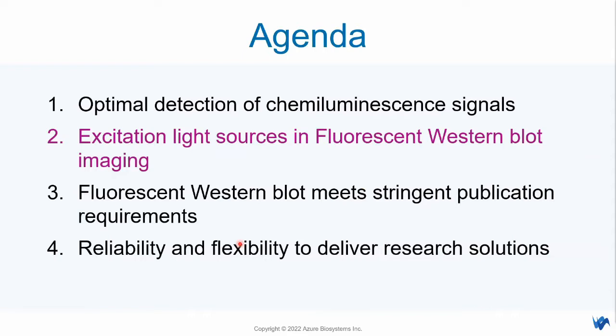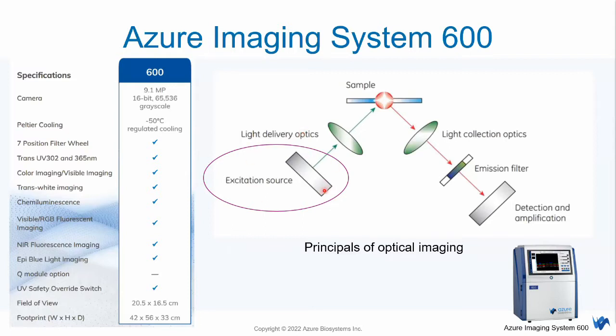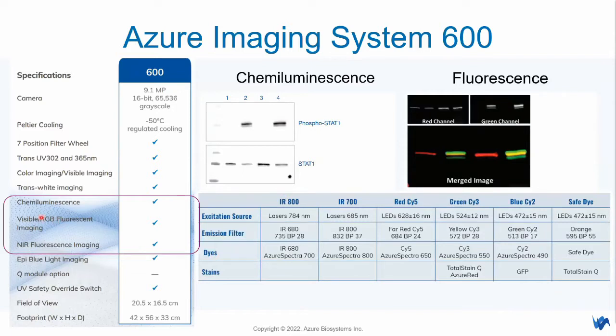Next, we move to excitation light sources. For chemiluminescent western blot, no excitation light sources are needed, but for fluorescence you definitely need them to excite the fluorophore. This system allows you to do RGB and near-infrared fluorescence imaging. We have two laser excitation light sources for the near-infrared channels, and LEDs for the RGB channels. You can see all the dyes compatible with these excitation light sources and emission filters, including safe dye and total protein staining imaging.